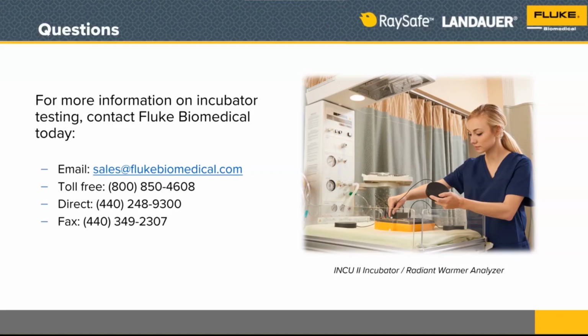And we test less often and we test fewer things when we do those safety tests here in the United States because we have such a huge amount of data collected, and we feel like we're still safe in creating safety when we're doing the tests on that basis. So here in the US, we would follow NFPA 99 and we would do those tests on incoming inspection or acceptance testing. That is when the infant incubator is brand new and it comes in. Even if we have another one just like it already, each time a new one comes in, we're going to do electrical safety testing. If for some reason the incubator went outside of the hospital for repair and came back in, we will do another incoming inspection, including electrical safety when it comes back in.